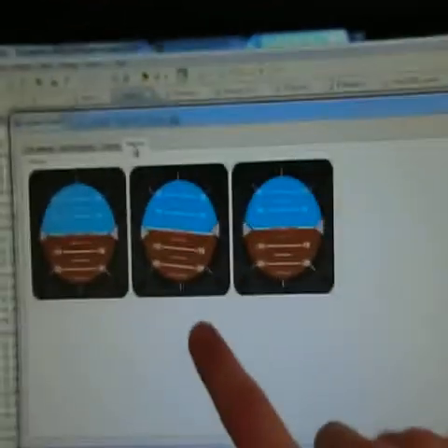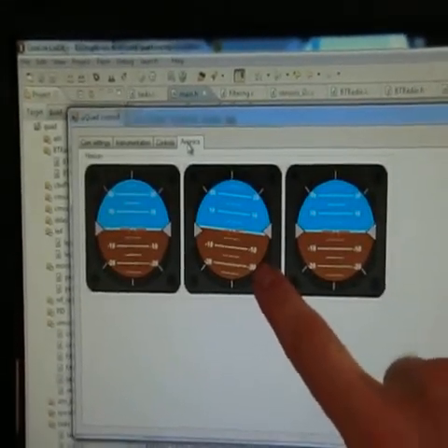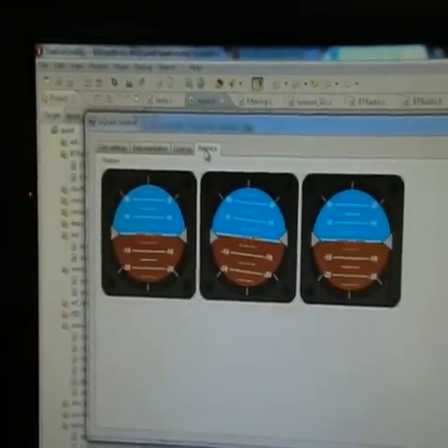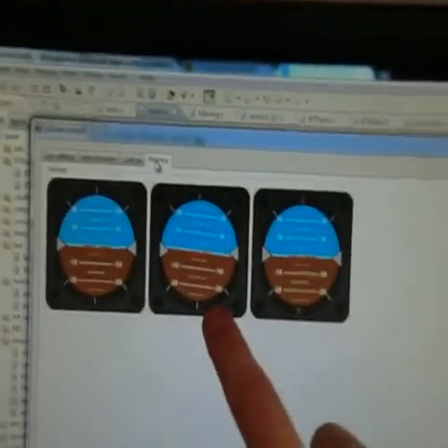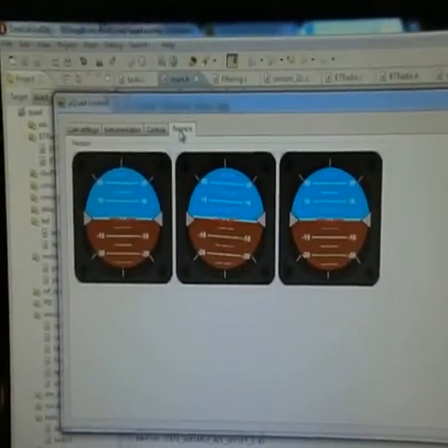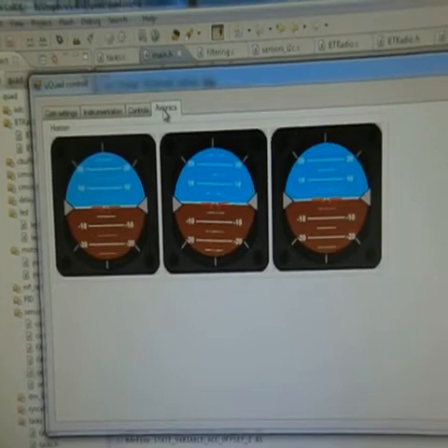I'm going to first fix the problems with the buildup. But whenever I fix that, I will start with the PID loops and see if I can make it correct. So now you can see that this one is slowly moving back. But it's moving back so slowly that it can drift enough to cause an overflow. So I will increase the drift rate of this one so that it drifts back much quicker. Because basically any behavior on this one at frequency lower than the corner frequency will be removed anyway. So I can 10-fold or 100-fold the rate at which it goes back to 0.